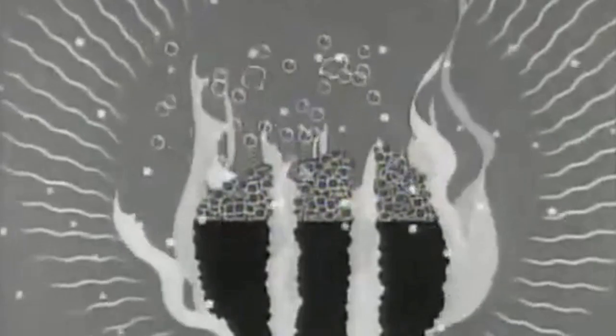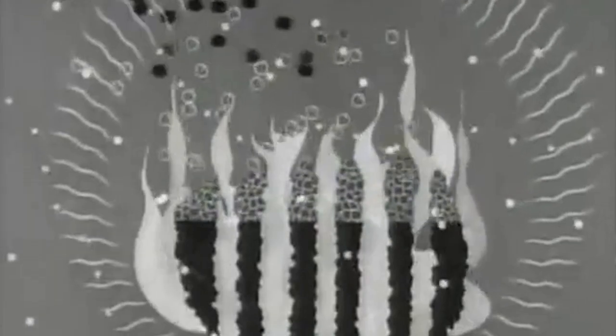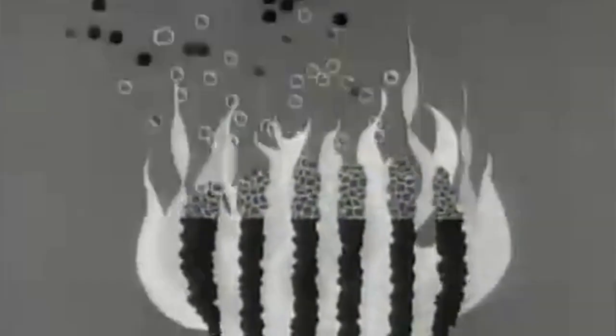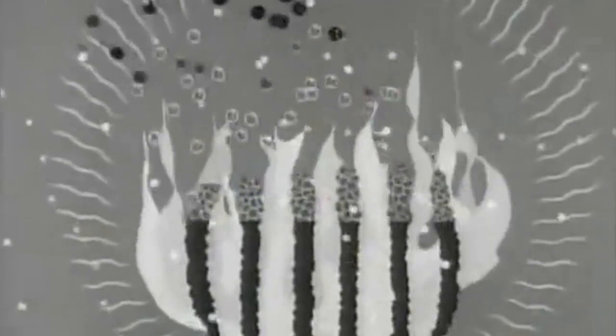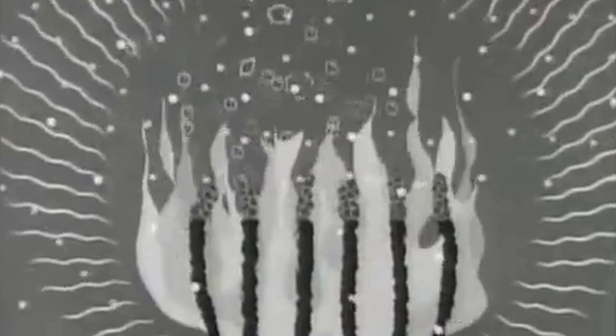The rate at which the coal burns away is partly determined by its size. It is said that no lump should be larger than a man's fist. Split into fist-sized parts, four more surfaces are exposed to the burning and the volatile gases are produced in greater volume. If the coal is broken smaller still, there will be more volatile than the air supply can cope with, giving dense black smoke. And when the air supply is increased, the coal burns away very quickly.